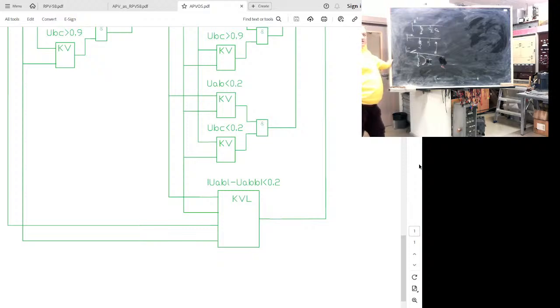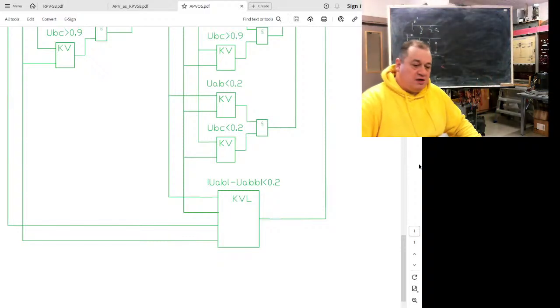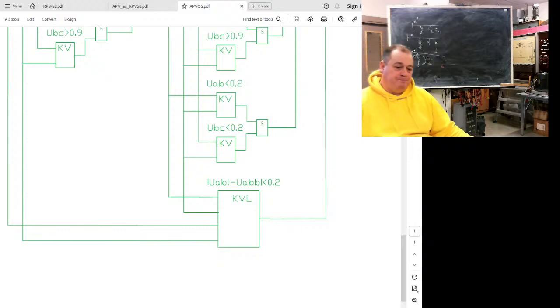So SPAR devices for such a line do one thing. They check line voltage for the presence of an oscillation signal. Some designs do send a disconnect signal to shunt reactors. Versions even exist where earth links are activated. If an oscillation signal is present, an earth link can be activated here. So SPAR checks for shunt reactor oscillation. Complex thing.